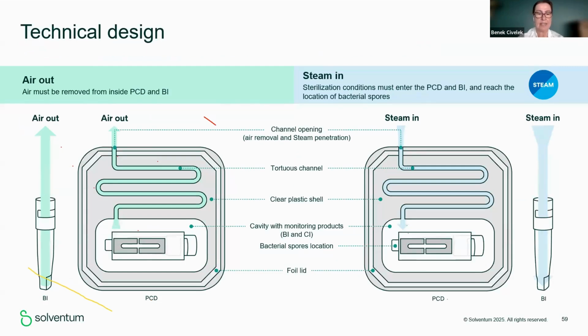The technical design is now lumen-based, and the challenge is a bit different. You see a more tortuous channel, but the idea is the same. We expect first in the vacuum phase that all the air is out, and when steam is inside, we expect the steam to perform inside the load, inside the chamber, and also get into this channel and reach the biological indicator and the chemical indicator. In pass conditions, we expect that the biological indicator is negative and type 5 is a pass in the accept window.